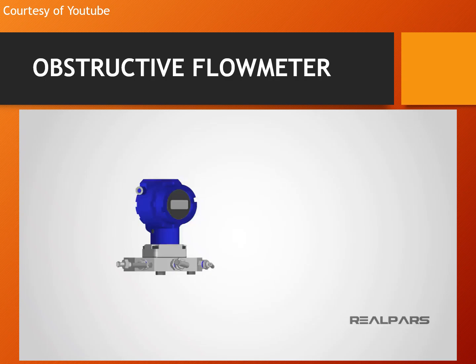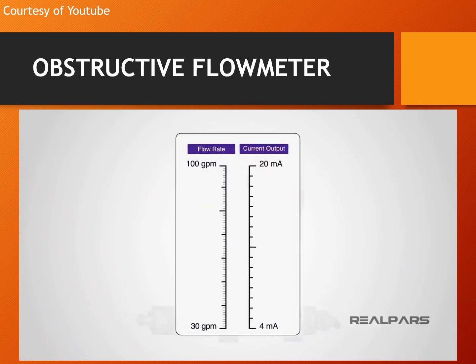Okay, let's go. We say that an instrument is calibrated when its output corresponds to a specific input across a specific range of inputs. Said another way, instrument calibration is a process where the instrument is adjusted in order to achieve the desired output range for a specific input range. For example, a current output type flow transmitter is calibrated for a volumetric flow range of 30 gallons per minute to 100 gallons per minute. When the transmitter produces a current output of 4 milliamps at 30 gallons per minute and a current output of 20 milliamps at 100 gallons per minute, a flow rate of 65 gallons per minute would produce an output of 12 milliamps.